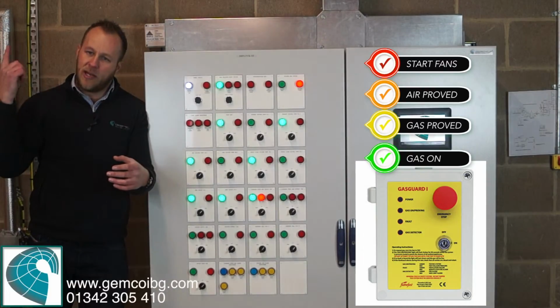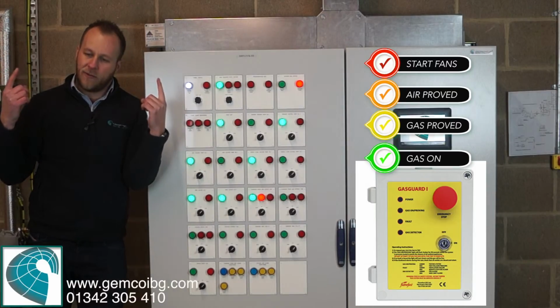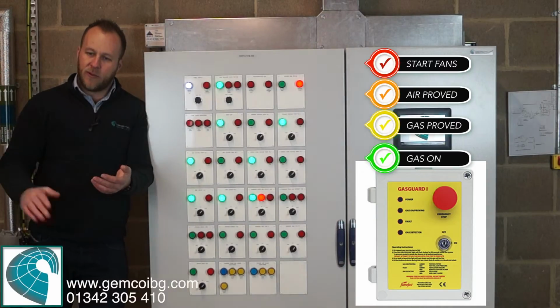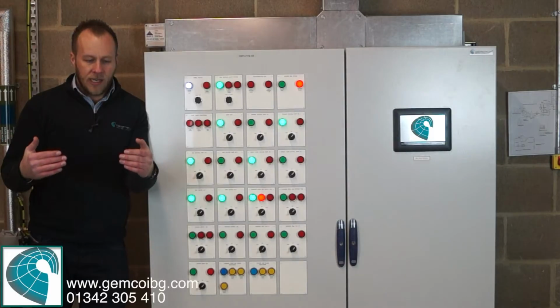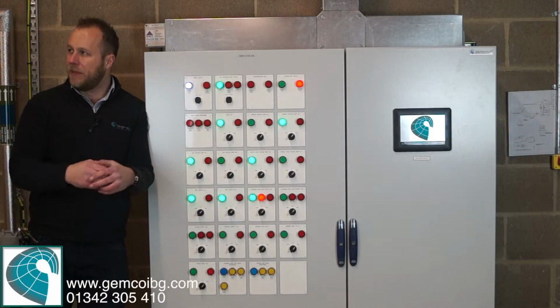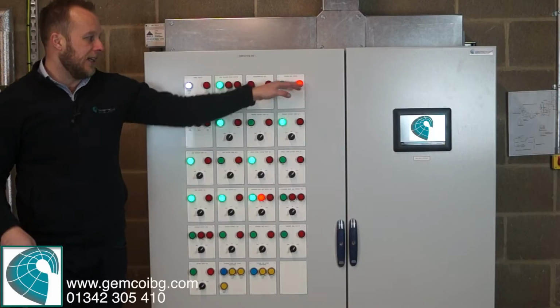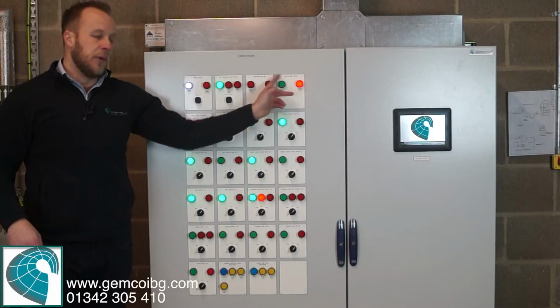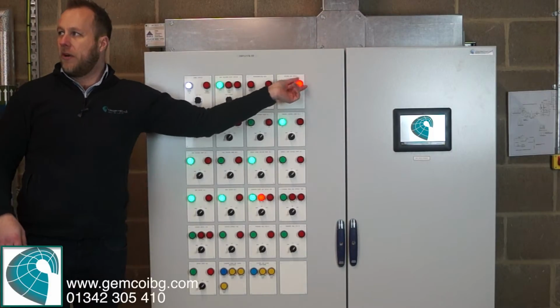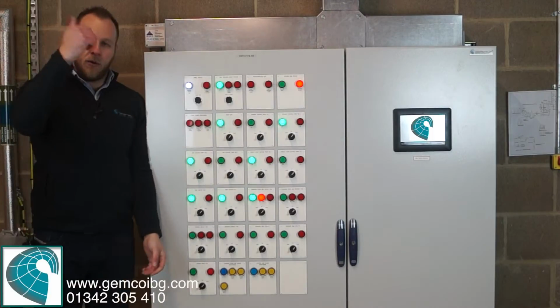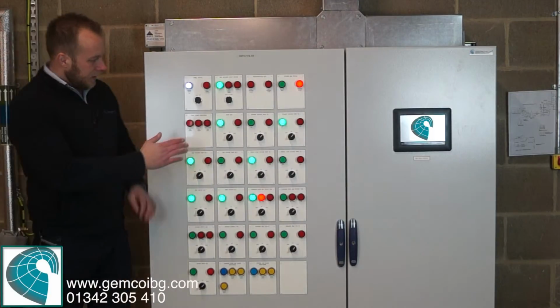So it will say, yes, I've got airflow on the supply, yes, I've got airflow on the extract, the gas pressure's fine, remain on. And if any of those aren't met, it will start beeping and you'll soon know about it. And all we do down here is monitor the status, whether it's open or closed. So they're not alarms, that's not a fault light or anything like that. It just says, at the moment, you've got no gas to the kitchen.